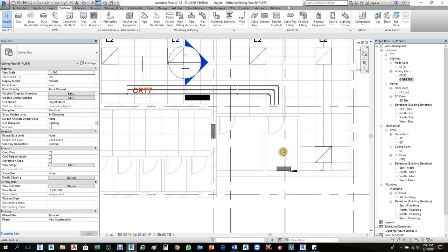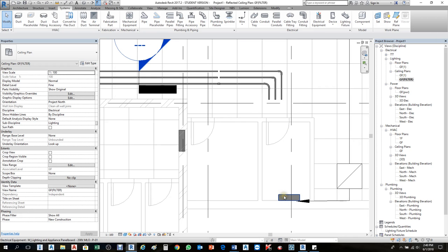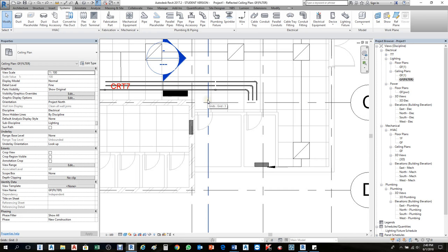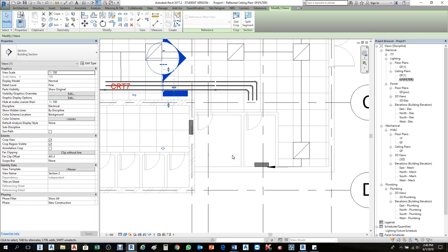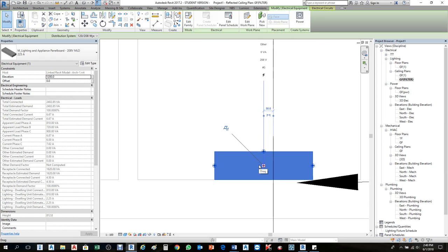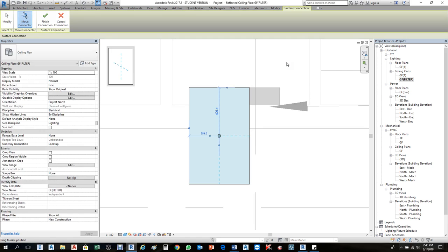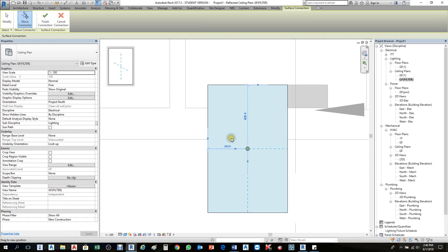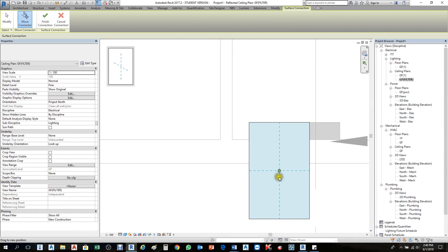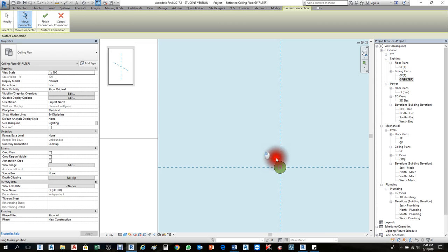Now I need to connect one conduit to the electrical panel. When you select the panel, you see three dots representing three faces from which you can draw conduits. Right-click on the desired face, then choose Draw Conduit from Face. A preview appears showing the panel — select Conduit and move it to the right or left as needed.